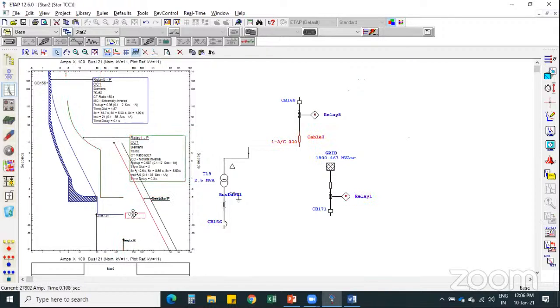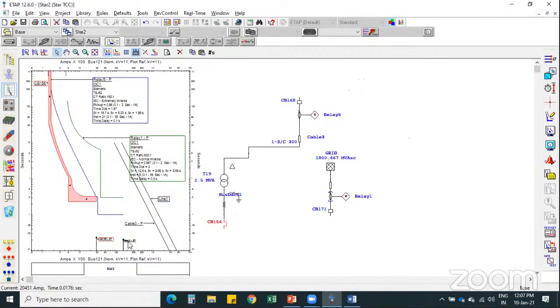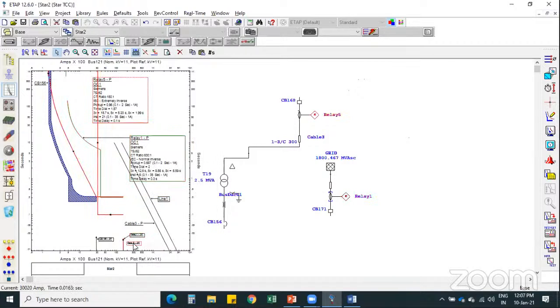This is the damage curve of the particular feeder, of the particular cable as well as the line, which are taken into consideration for this portion. This is the fault current indication, that is, how much fault current will persist in the network whenever any fault occurs in the system. You can see that for both the relays. See, this is for the LV section bus, LV section circuit breaker. This is for the upcoming incomer relay. This is for the incomer relay.